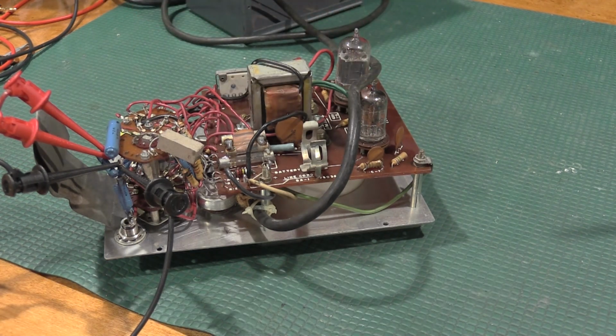There is a specific in the RCA manual, if you have to replace the tubes, there's an aging process before you should even calibrate this meter. The tube should be aged, hyper-aged, 24 hours, or the meter should run for 3 to 4 days with the fresh tubes in circuit before a calibration is done on it. I think that's for long-term stability of the calibration, as the tube ages very rapidly when it's fresh. Some of its gain falls off in the beginning, but then it'll sustain this gain for quite some time and have a good long-term turnaround. So I'm going to put him back in the case because I think we're ready to power it up.